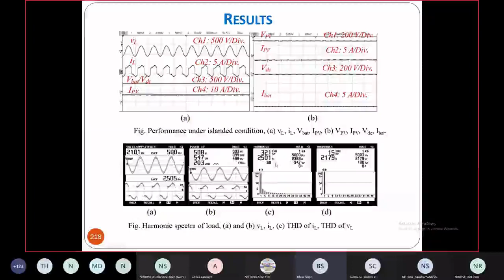Then, typically, when the grid appears, the load is not affected because you have a battery and possibly solar generation, so load voltage and current are already present. But when the grid appears, you have to synchronize the entire system to the grid.